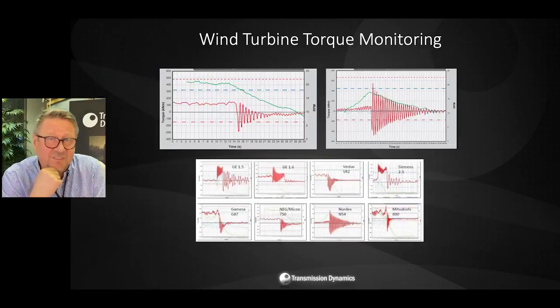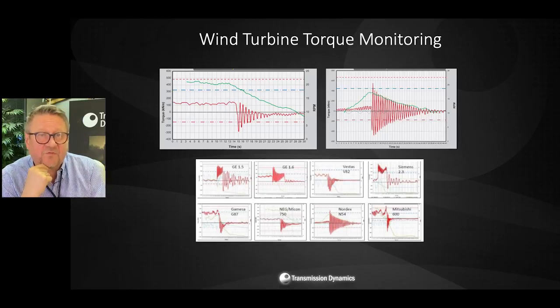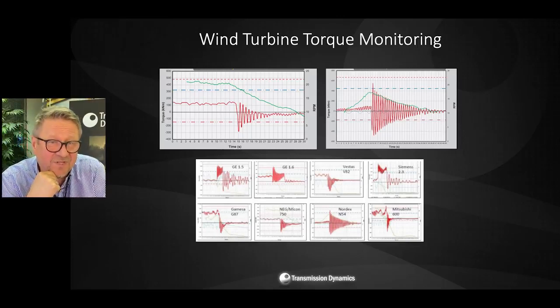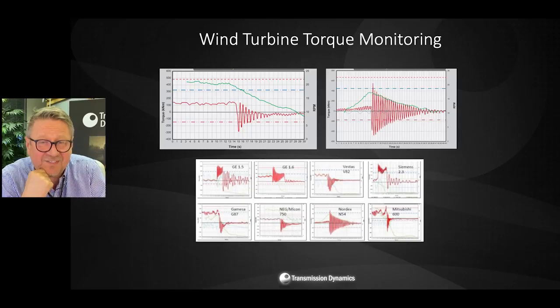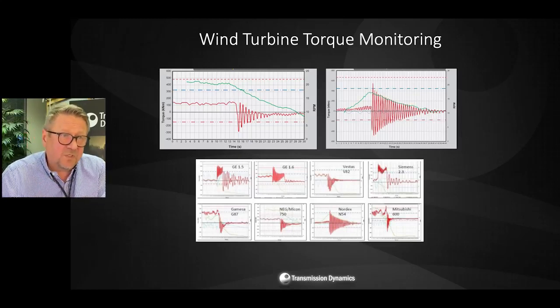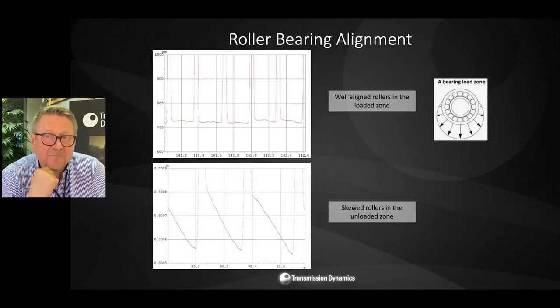On the next slide, you can see the wind turbine survey. You can see that surprisingly there is a significant number of wind turbines suffering from torque reversals. Here we've got the GE 1.5, GE 1.6, Vestas V82, Siemens 2.3, Gamesa G87, Micon 750, Nordex N54 and Mitsubishi 600. They are all exhibiting the significant occasionally and sometimes sustained torque oscillations during transient conditions. On this occasion it will be shut down. On some occasions it will be effectively start up when we assign the turbine to the grid. And what is happening during that process is shown on this slide here. On the right hand side, that little inset explains it all.